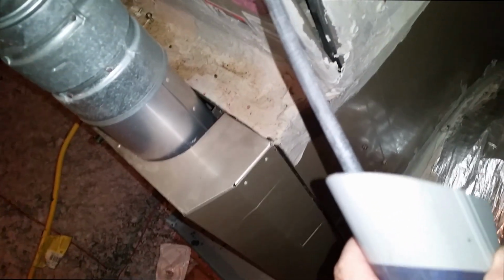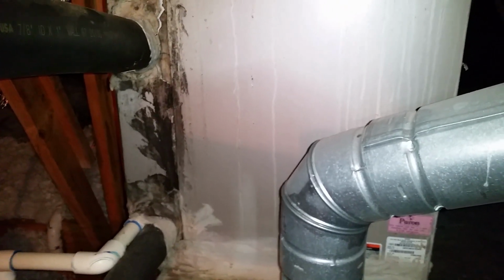And so I do this by performing a refrigerant leak search, because I determined that the unit was low on refrigerant. I'm performing this test to determine if that coil is leaking or not, because when the refrigerant leaks out, it doesn't always show. Here I'm getting ready to replace that coil because I discovered that it was leaking refrigerant. This is just showing a before picture before I replace that coil. I believe there's another view here coming up where I've got the panel off. Yeah, here panel is off, and so you can see how rusted that coil is.